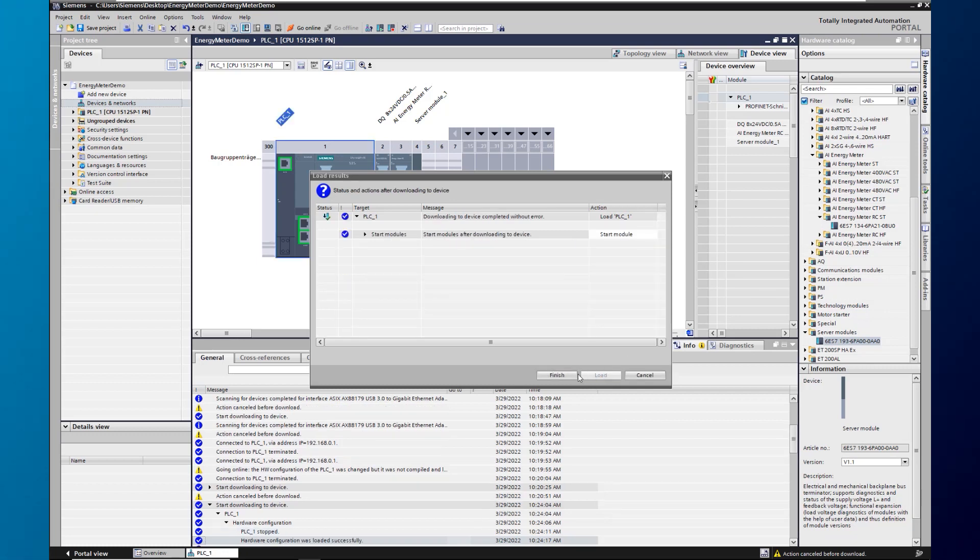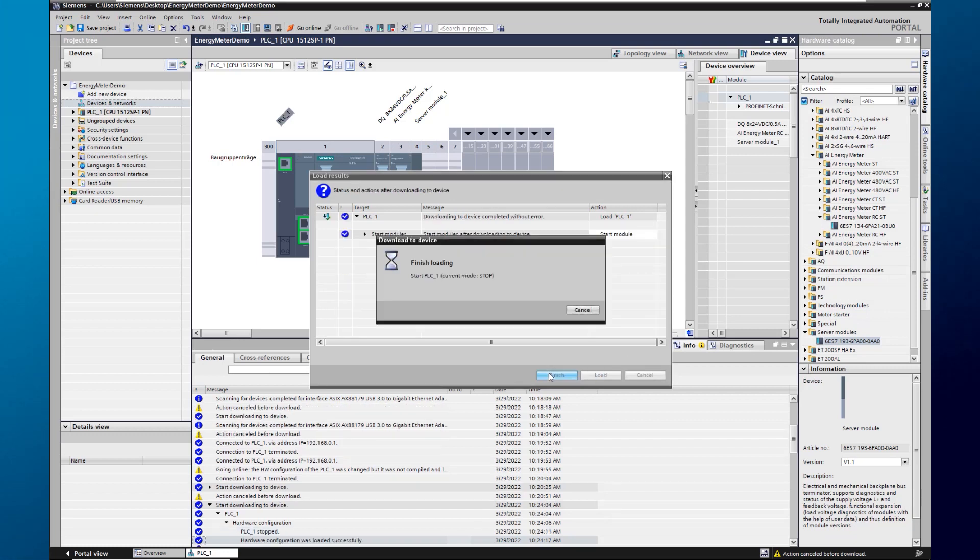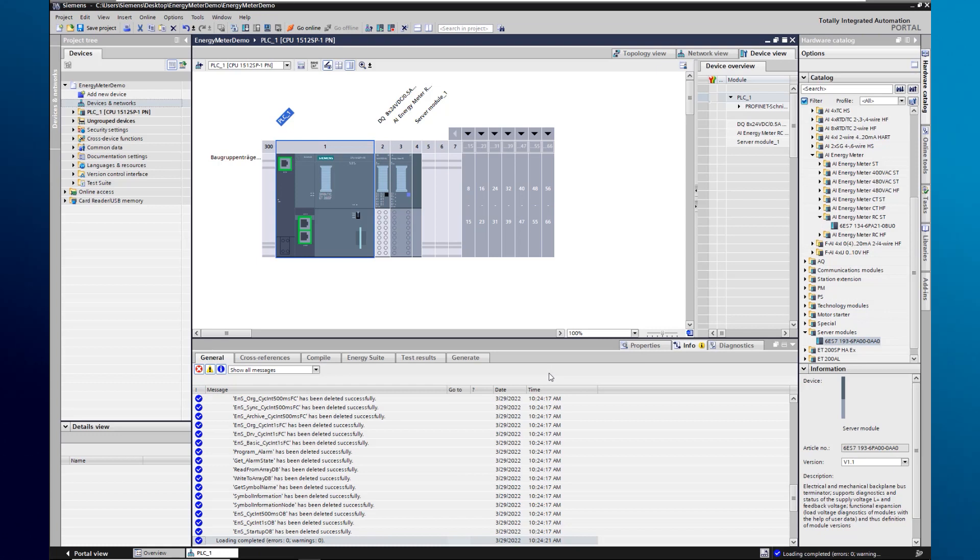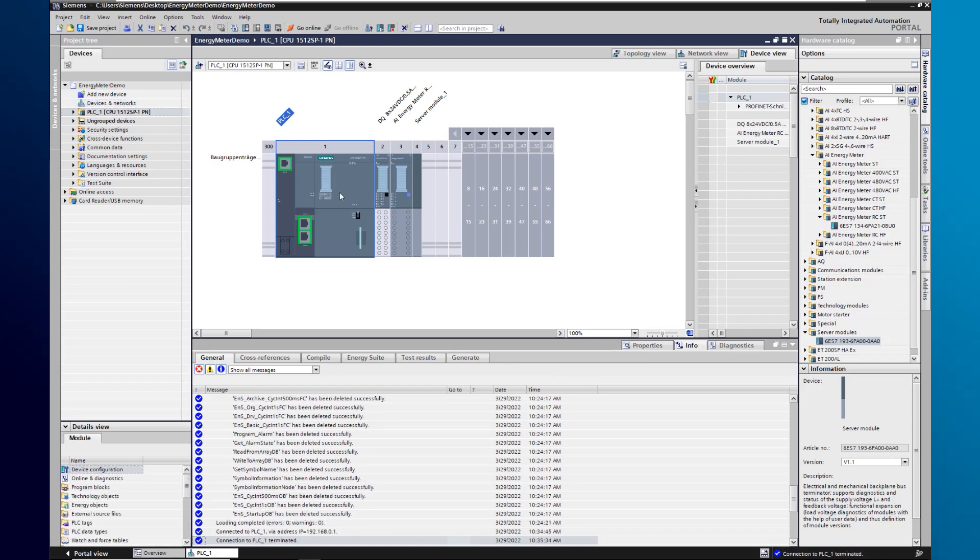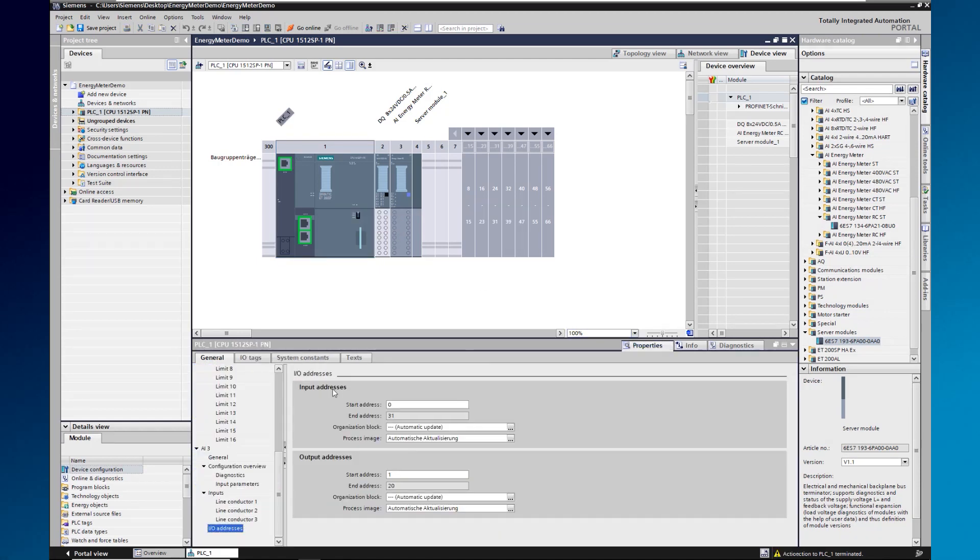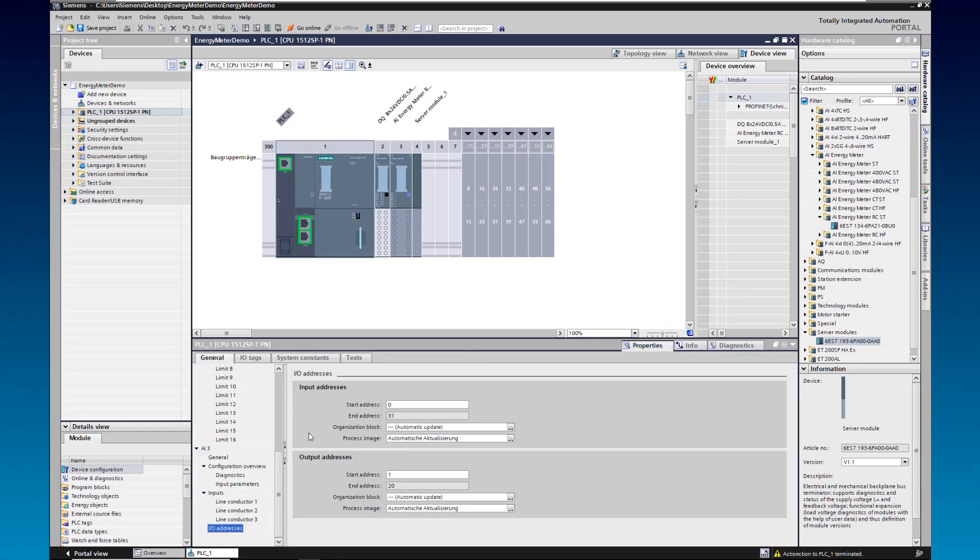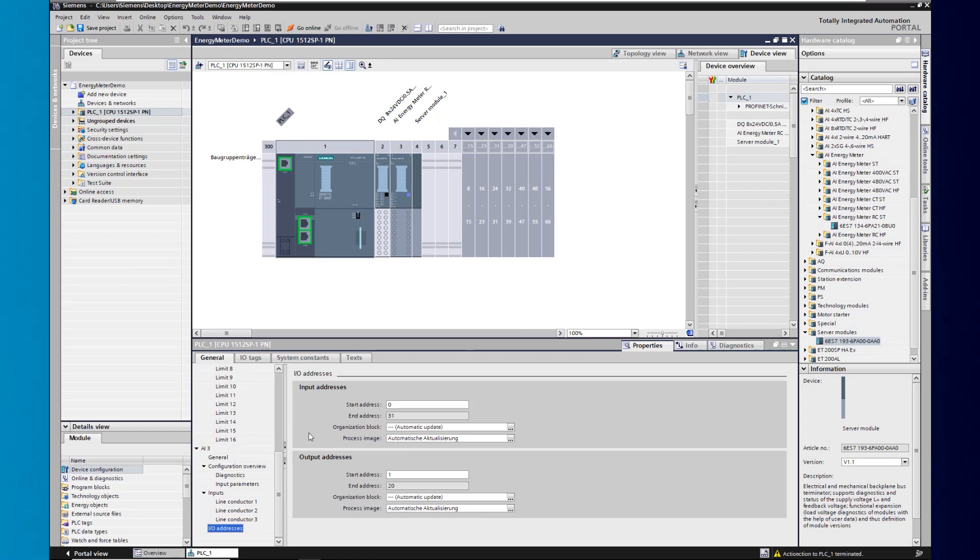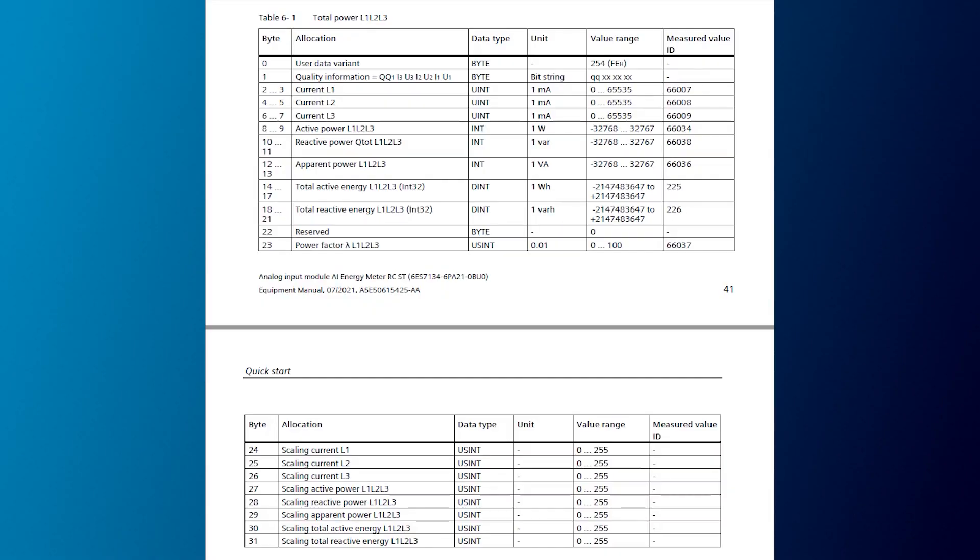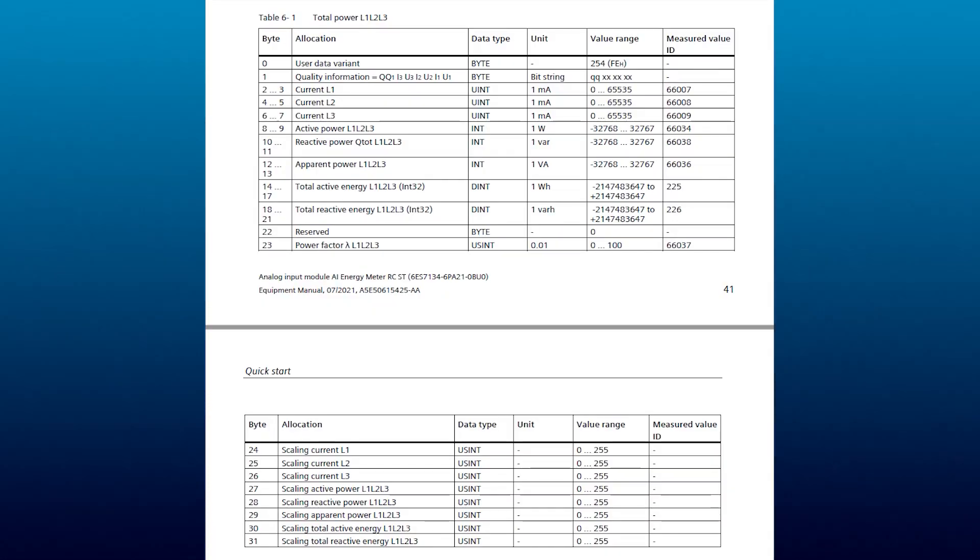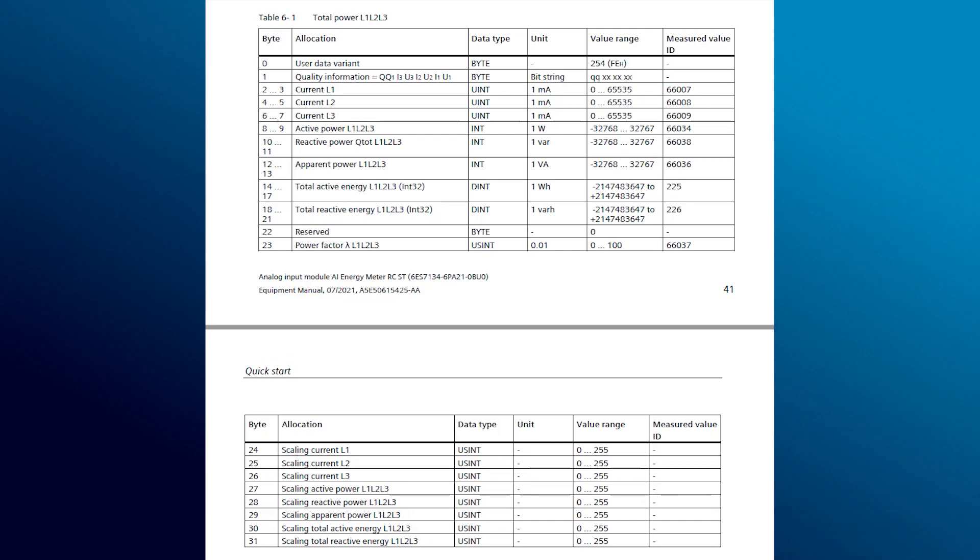To have a look at the data, we can store the data in PLC variables. For this, we get the data from the periphery address. In our case, the currents of the phases as well as the total power are on the input address 2 to 10. You can find out which value is at which position in the quick start chapter of the manual.